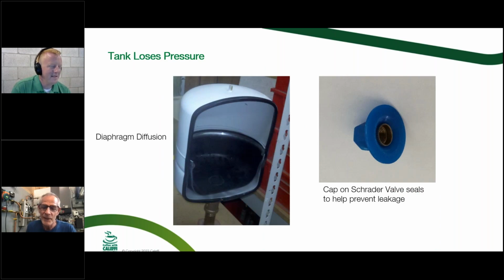Yeah, so the cap on the bottom, as you can see in that one, has a Schrader valve like you would have under your tire stem that you can tighten up and seal off. So if you think the Schrader valve someday might leak out air and lose your air charge, tighten the cap when you're done. And there you can see the diaphragm. There's a cinch ring or some kind of ring that locks that diaphragm in the tank. That's what the one groove in there is.